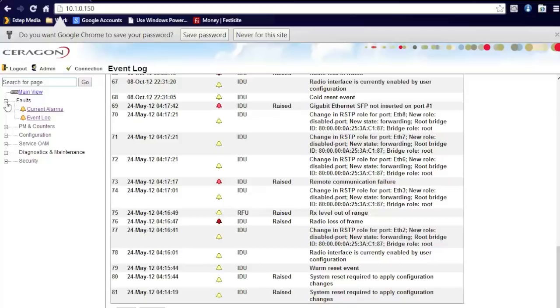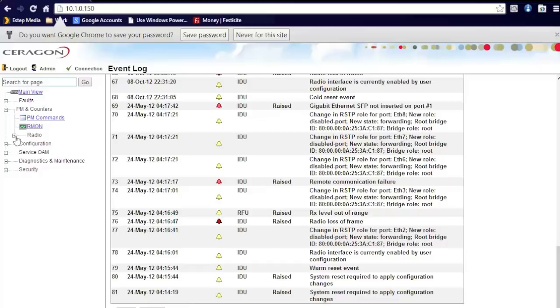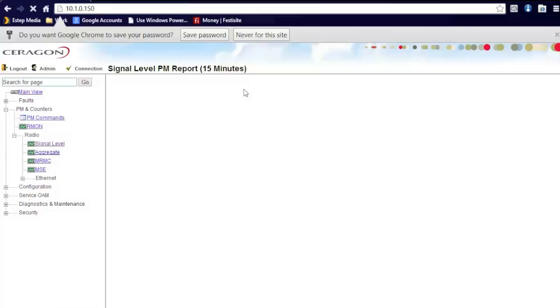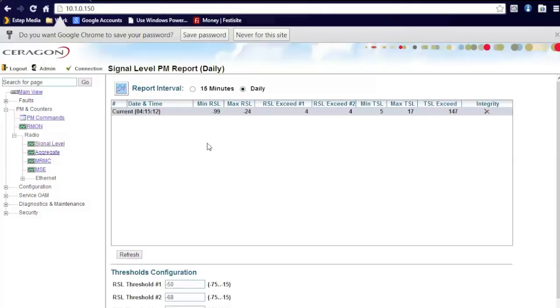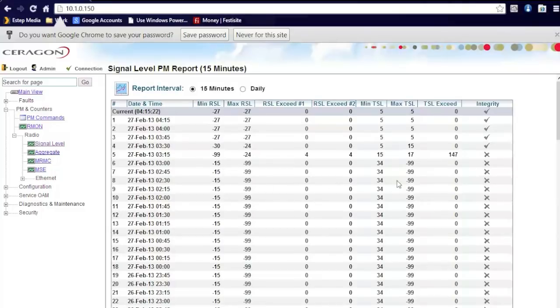We'll move on down here to PM & Counters. Basically here, this is where you can view the signal level for the current day as well as you can view it over time. This will hold up to 30 days of logging in this daily report here. Currently we only have a couple hours of information. So you can actually see here the integrity on the right are actual events that we can count on that were legitimate events in the logs.